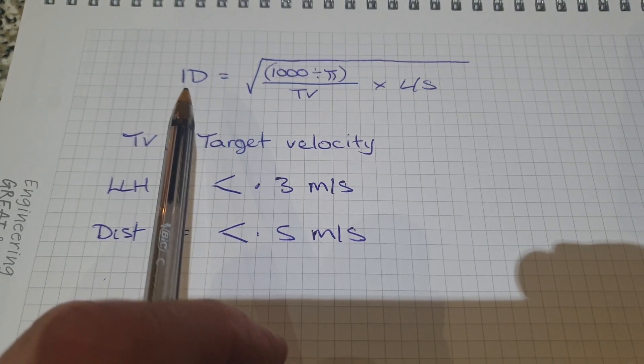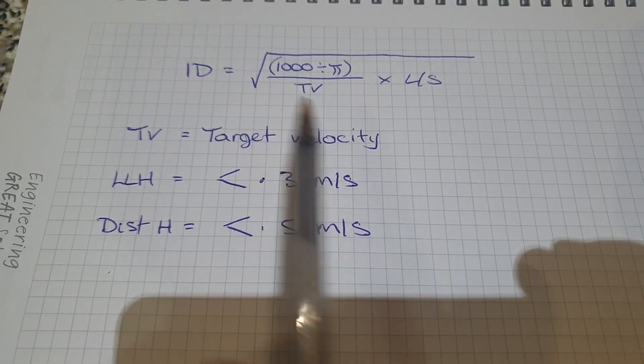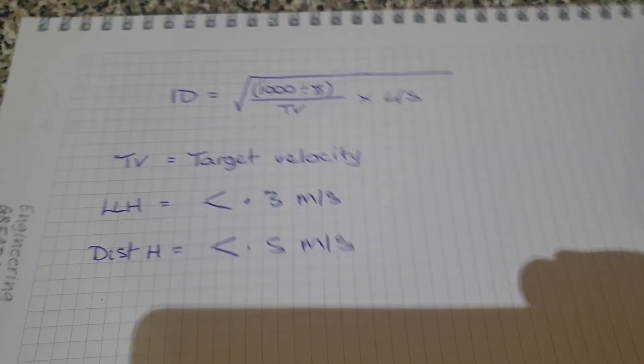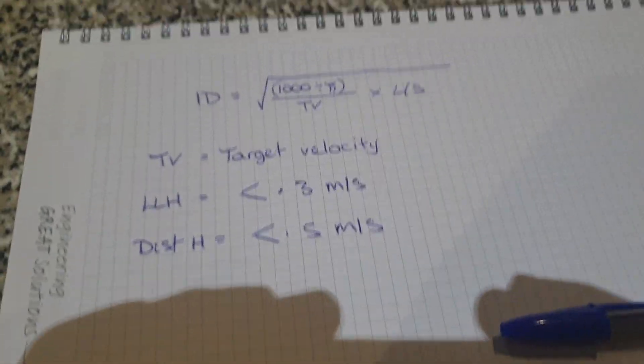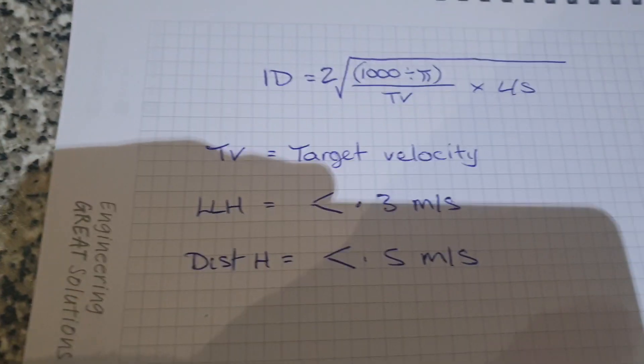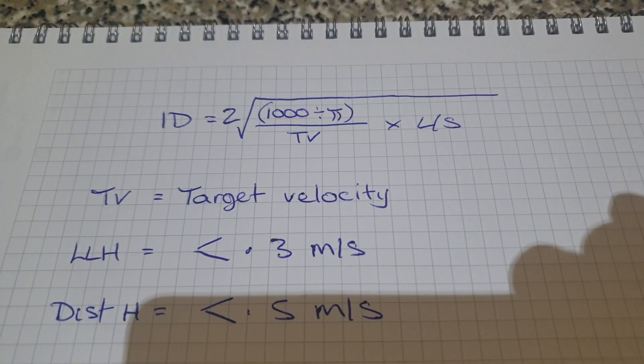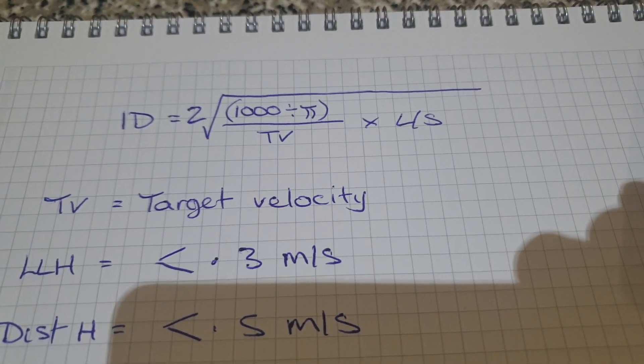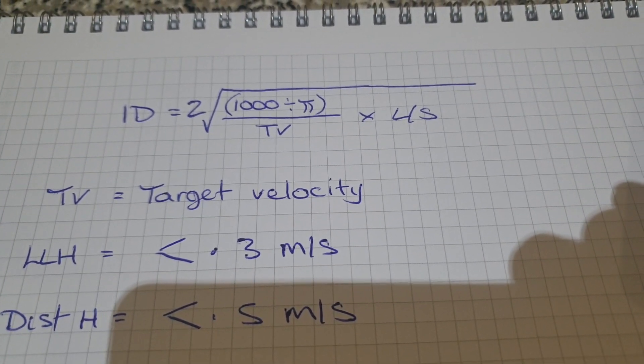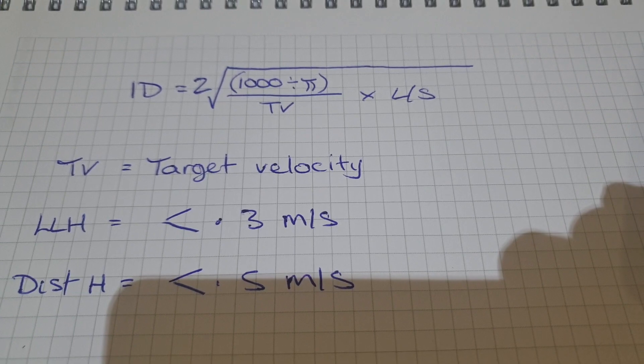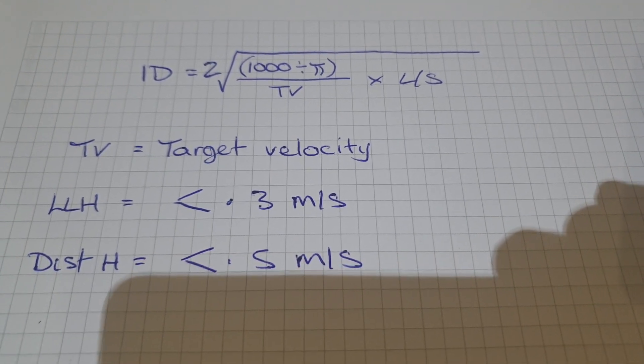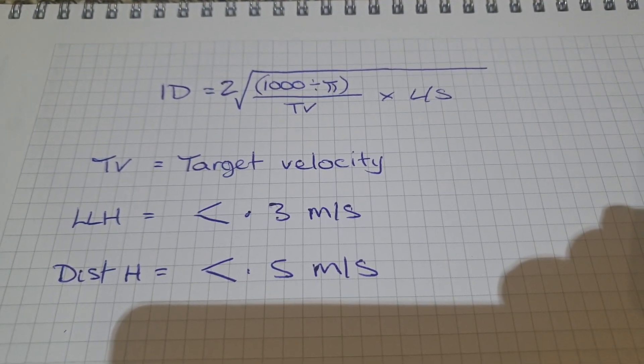But anyway, this formula is quite simple. So the internal diameter of your pipe that you need is equal to 2 times the square root of 1000 divided by pi divided by the target velocity multiplied by your liters per second that you've got from your mass flow rate calculation.